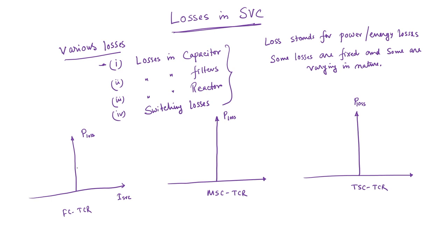In general, the fixed losses in fixed capacitor TCR are usually higher. This is the amount of fixed losses, and it tends to be higher. The reason, as already discussed, is that in fixed capacitor TCR, capacitors are always turned on, so there is circulating current between the capacitor and the TCR units, which constitutes certain losses due to this loop current.